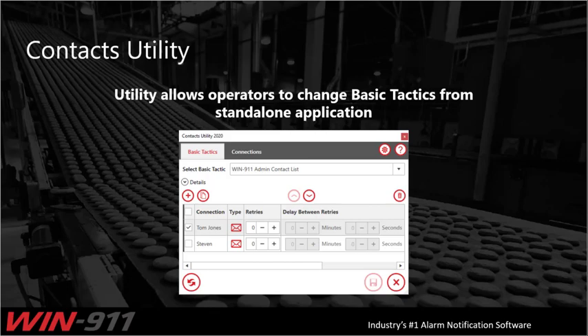Last year we released the Contacts Utility, which allows operators to make changes to the call-out list and their schedules without needing to access the full WIN911 configuration in the workspace. A lot of people wanted this so they didn't have to train people or give access to open the workspace and change the tactic. You can create a button on your InTouch side that launches the utility — a lightweight separate executable — where you can change the tactic, the call-out order, and the scheduling. That's all it gives permissions into, so your operator never needs to leave the HMI and can't make any extra changes that might cause issues in WIN911.